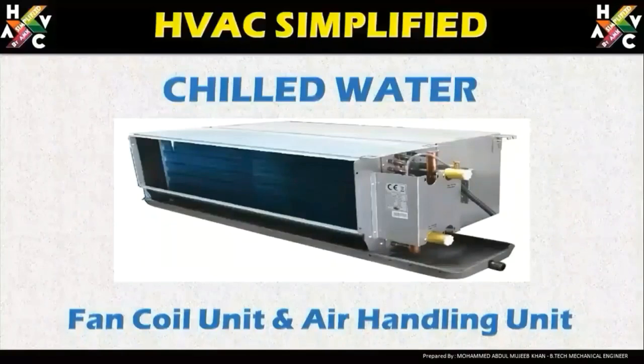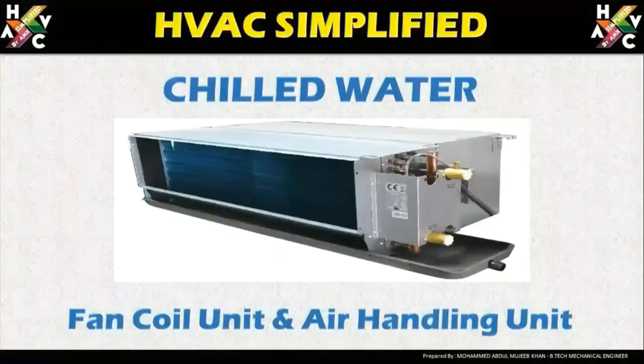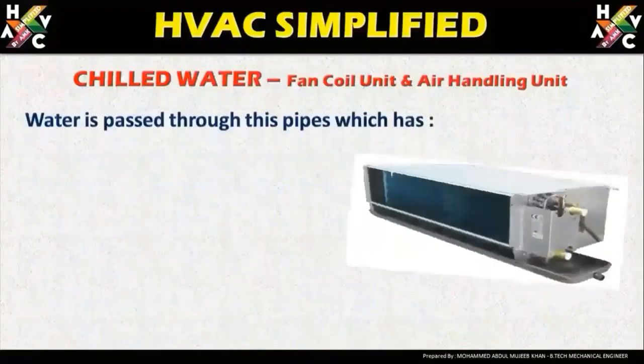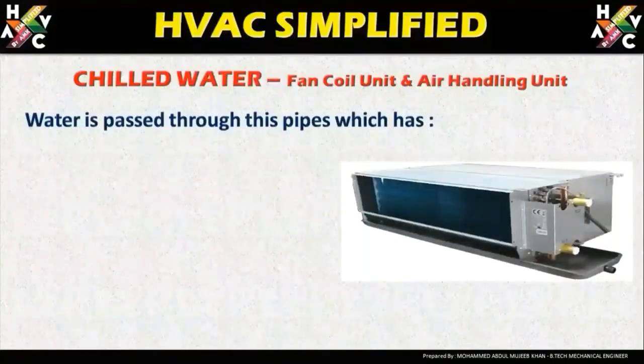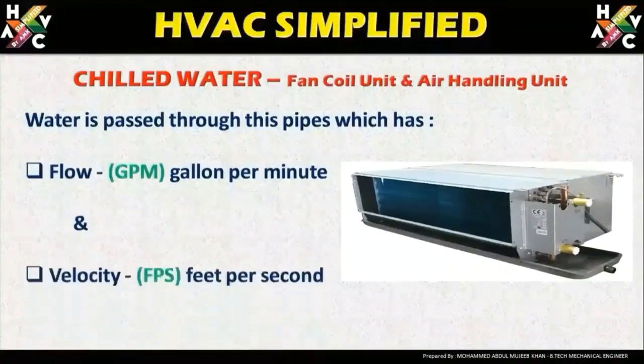For any chilled water air handling unit or fan coil unit, you need to find the GPM depending on the design criteria. The following parameters are required, which we can derive after getting the capacity of the fan coil unit and the air handling unit. Water is passed through the pipe, which has flow in GPM and velocity in feet per second.